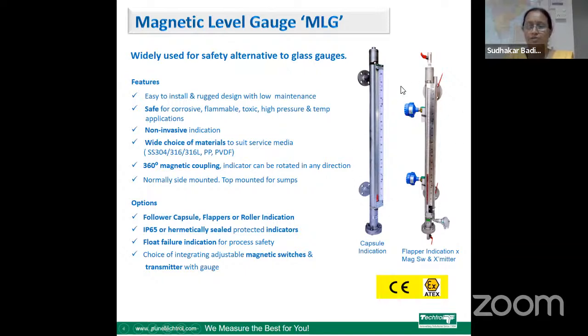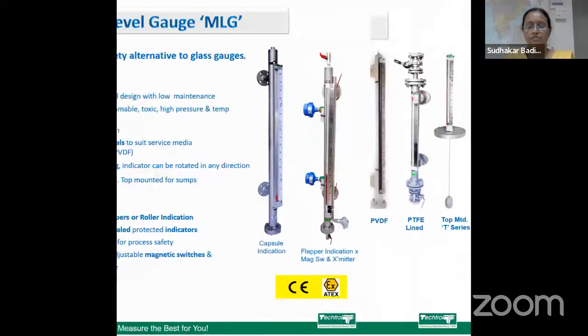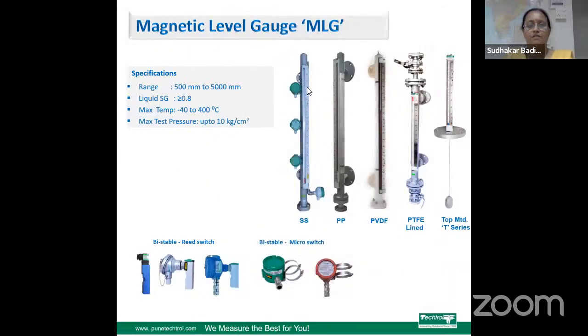So on the left hand side, you can see the level gauge with capsule indication, and on its right, the level gauge with flapper indication, which is integrated with the switches here. And this is the transmitter. This gauge is available for a CC distance of 500 mm to 5000 mm. It is suitable for a maximum temperature of 400 degrees Celsius and pressure of 10 kg per centimeter square.